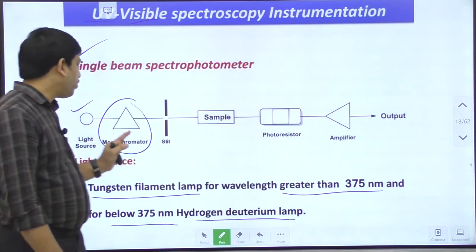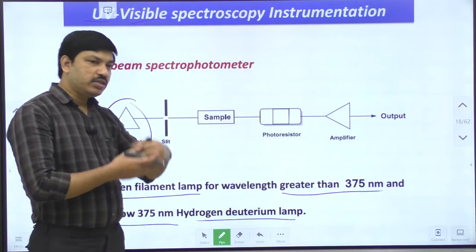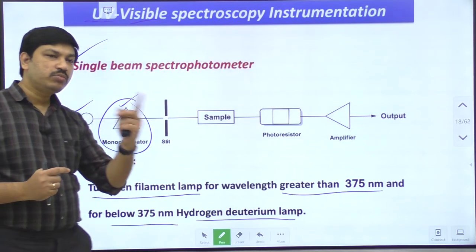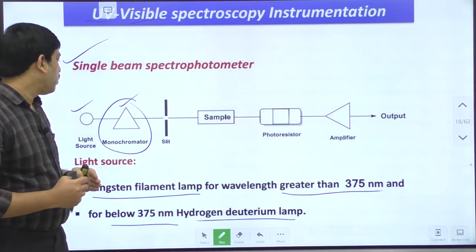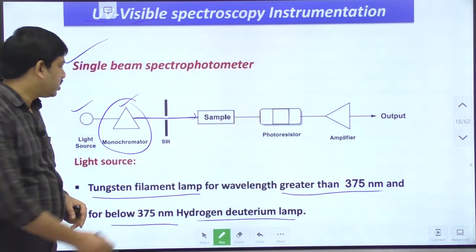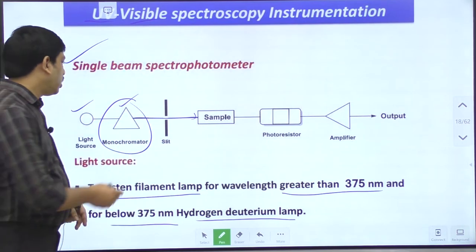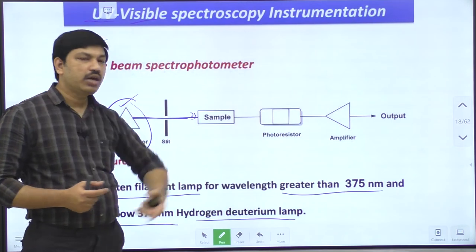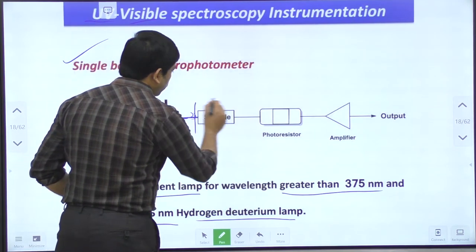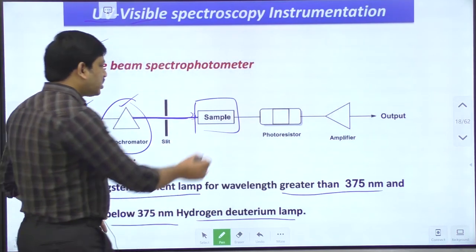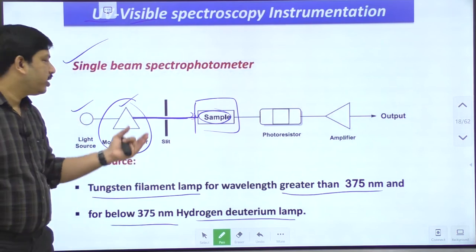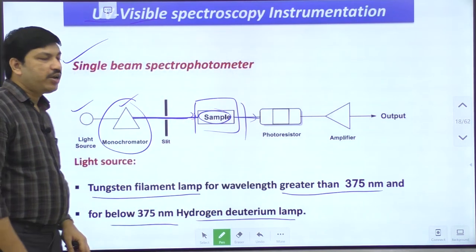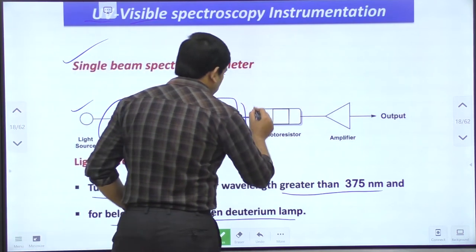The light then goes to the monochromator, which is a combination of an entrance slit, a grating, and an exit slit. The main purpose of the monochromator is to send a single wavelength of light towards the sample — it splits the radiation and sends singly polarized, monochromatic light to the unknown sample. That light goes to the sample holder, and depending on the nature of the molecule, the sample absorbs some particular radiation while the remaining radiation comes out, which is called transmitted radiation, and the incoming light is called incident radiation.